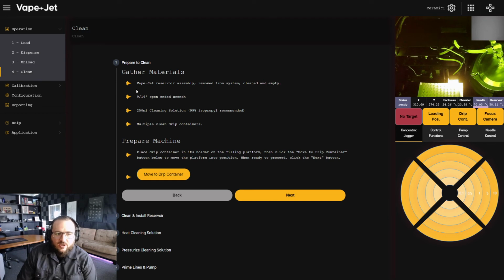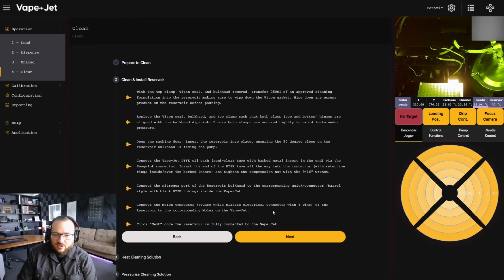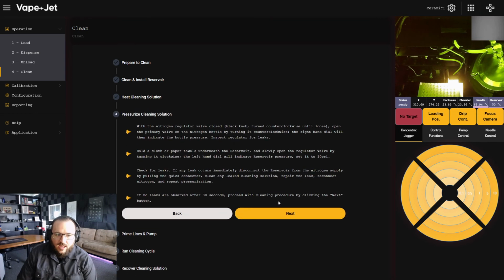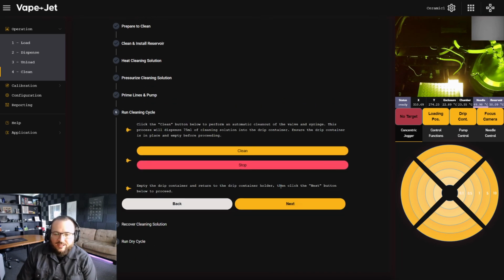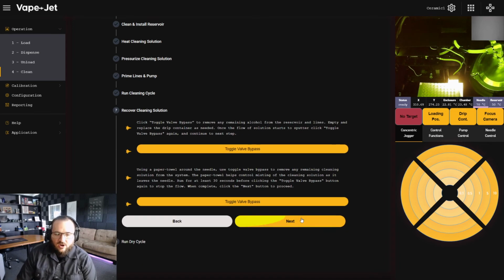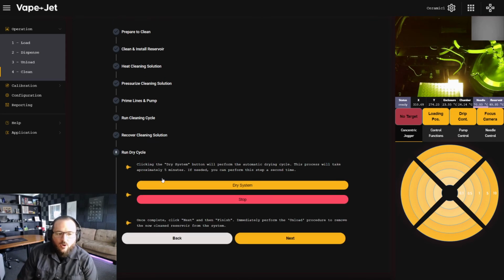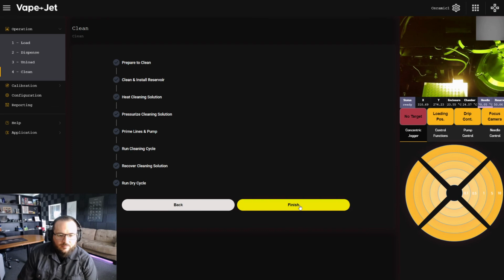Once that's done, you load the system with a cleaning solution and walk through a wizard that guides you through a clean-in-place procedure. When you get to the cleaning cycle, you hit clean and walk away for 5 minutes while the system does a self-clean. Again, all these wizards provide step-by-step instructions, and all the buttons you need to press are brought directly to you. Once cleaning is done, you also run a drying cycle, using nitrogen to blow out the system.